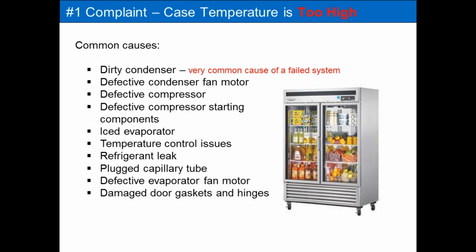We're going to talk about dirty condensers, which by far is a pretty common reason for failures of these systems. Whether the condenser being dirty is the immediate failure, or the condenser being dirty caused another failure, for example, a defective compressor.